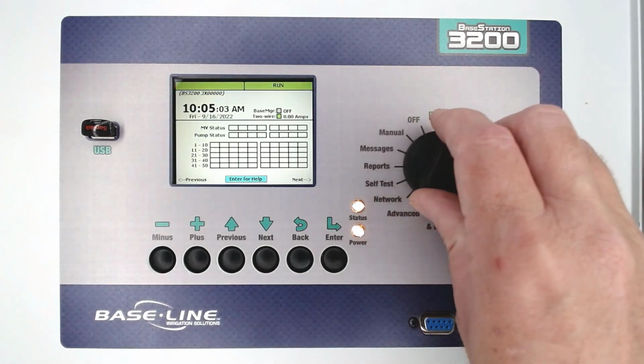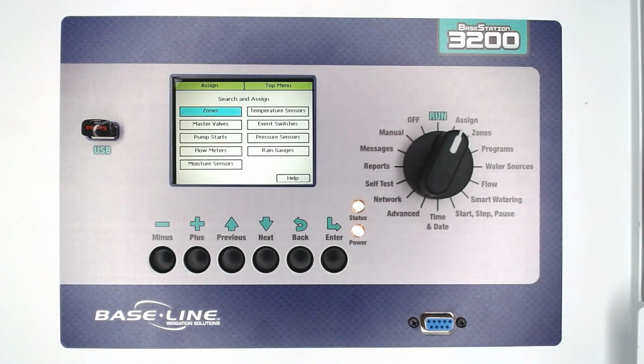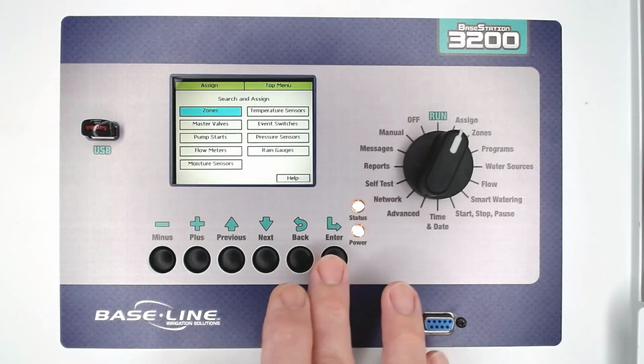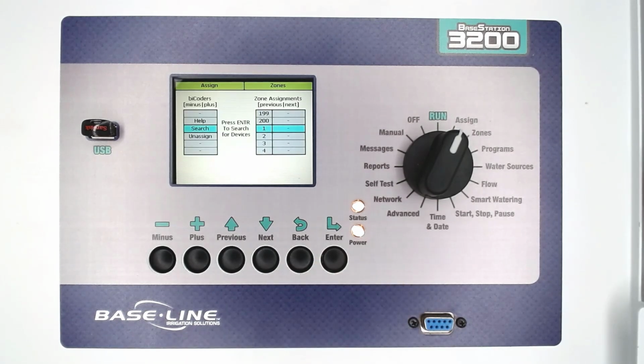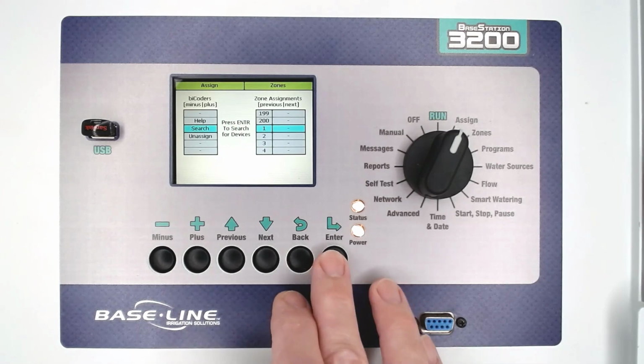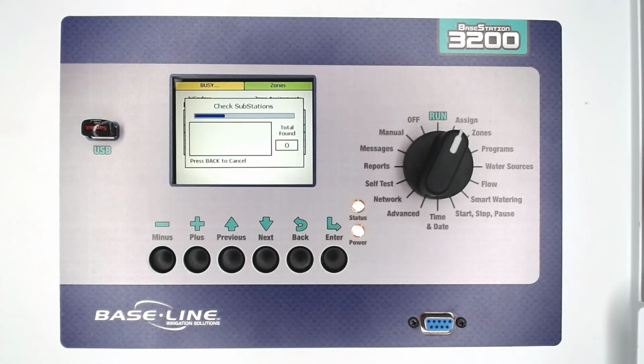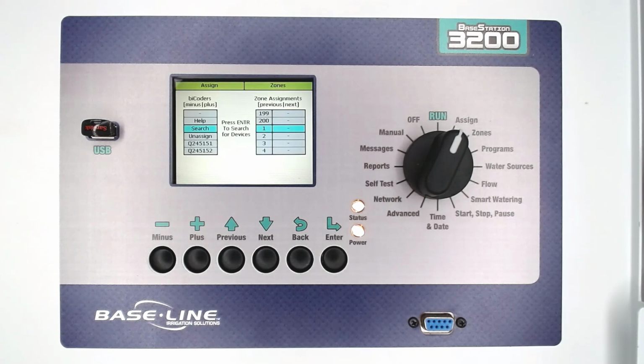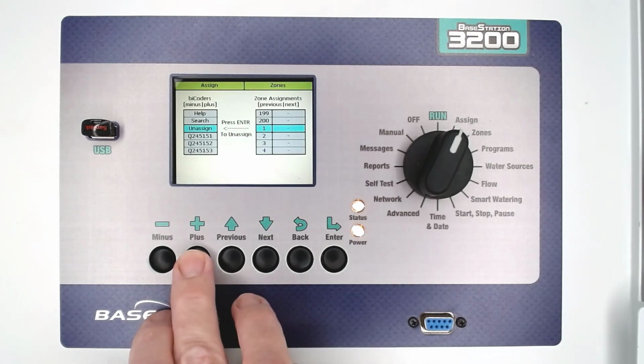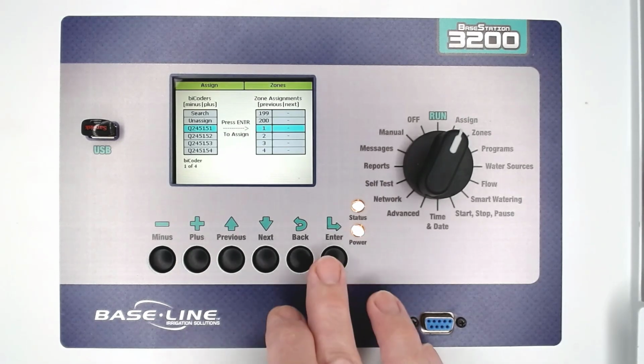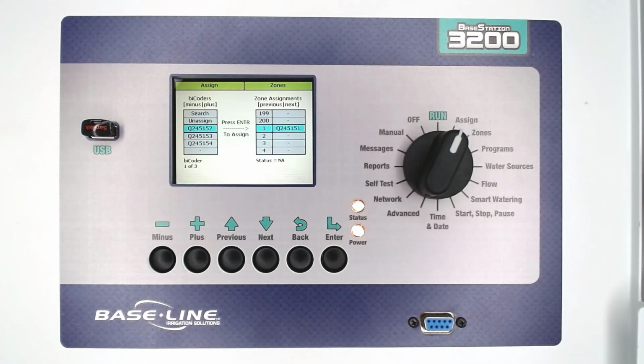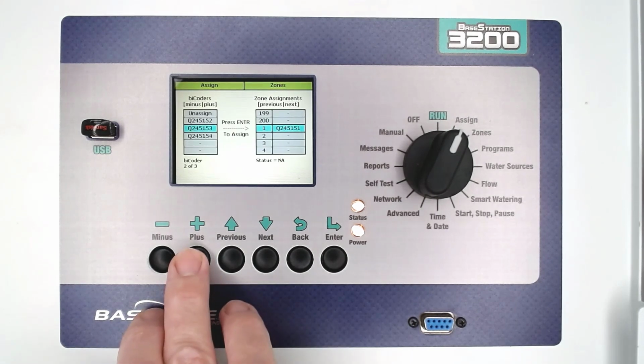At the controller, turn the dial to the assign position and open the type of device you're looking for. I'll review zones for right now. With search highlighted, press enter. This starts the search of the controller for any connected devices. Once the search is complete, the list on the left is populated with serial numbers from the wire path. Now it's just a matter of transferring those serial numbers to the right side of the screen. I've just assigned serial number Q245152 to zone number 1.